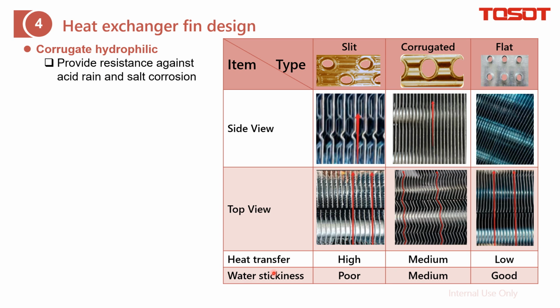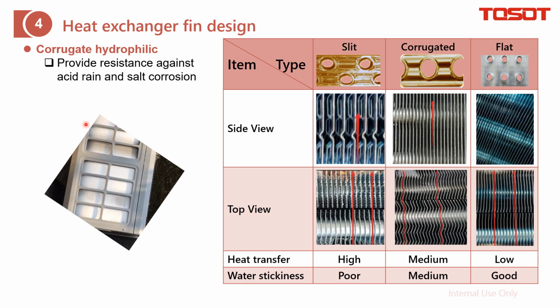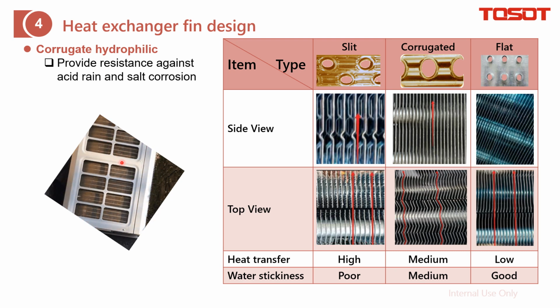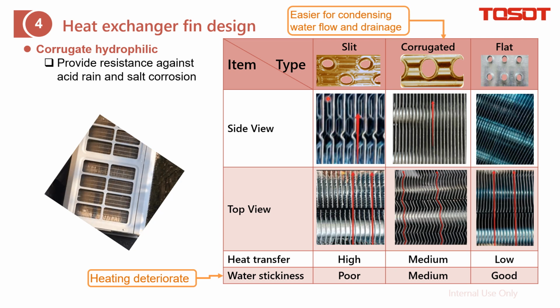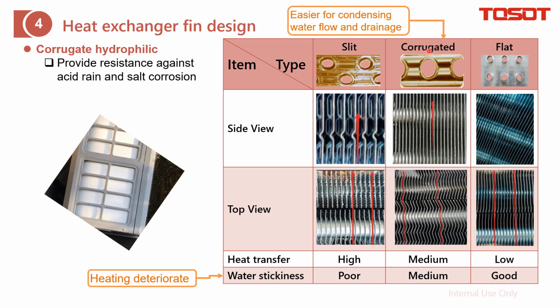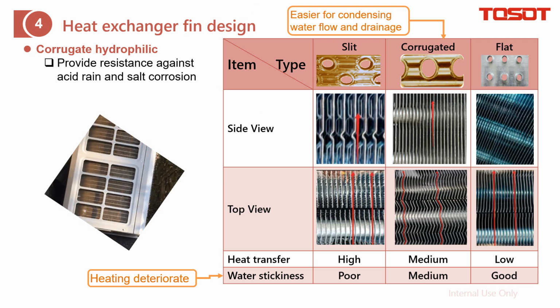And the reason is, in heating mode, the outdoor unit will always generate condensing water, right? Especially when the outdoor ambient is lower than the freezing point, it will generate frost or ice, and then we need to do the defrost, which is to make the ice become water. And if this water can easily stick on the fin, it will not be good for the next heating cycle because it will quickly become ice again. So for the water stickiness, the worst one is the slit fin because the water can stick on the slits, and the best is of course the flat fin, but considering the heat transfer efficiency, we will choose this corrugated fin as the UNIX outdoor condenser fin.